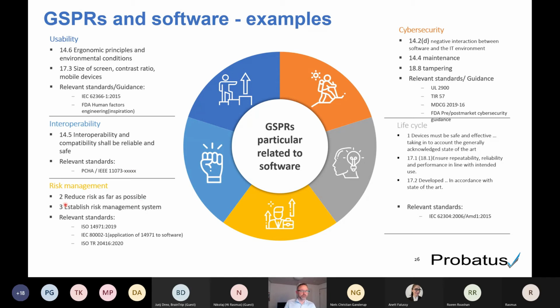Risk management. Requirement number 2 is to reduce risk as far as possible, and number 3 is to establish a risk management system. This illustrates that it is really important to have risk management in scope of all activities. The relevant standard here is the 14971 from 2019. That is the risk management standard to use. When we're talking about software, there's a technical report, IEC 80002-1, which describes how to apply the 14971 standard for software explicitly. Then there's also one for the post-market surveillance part, and I'll address that later, the 20416 standard, which is also relevant in that context.